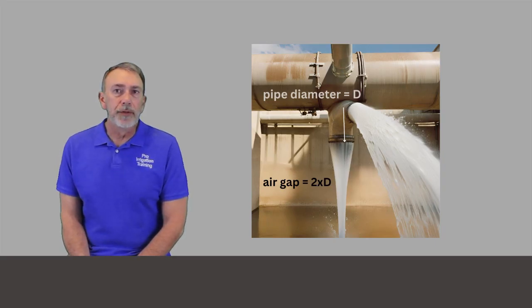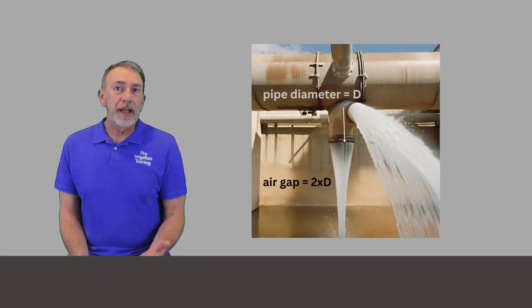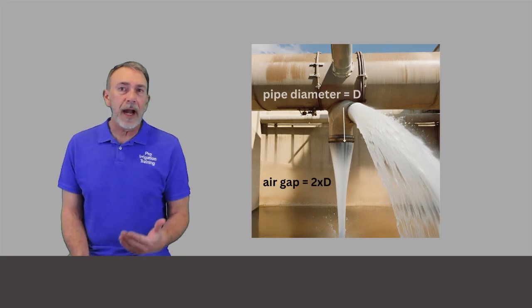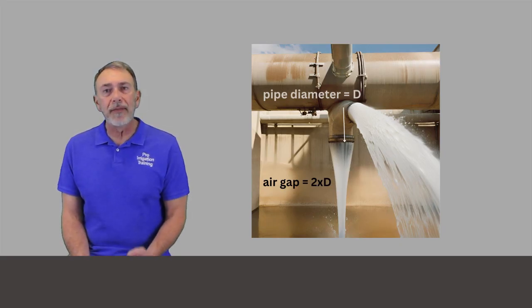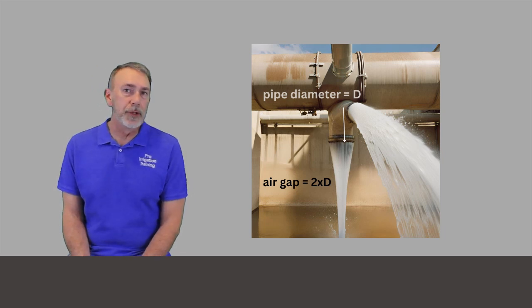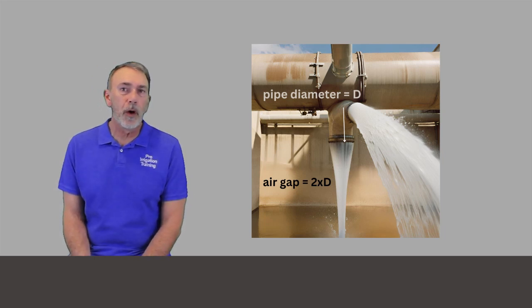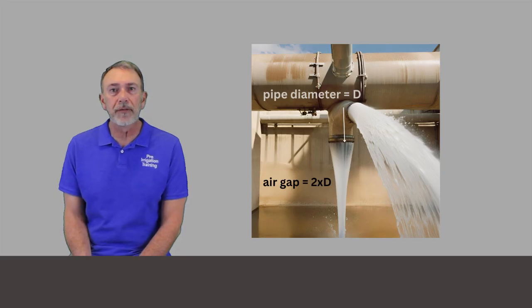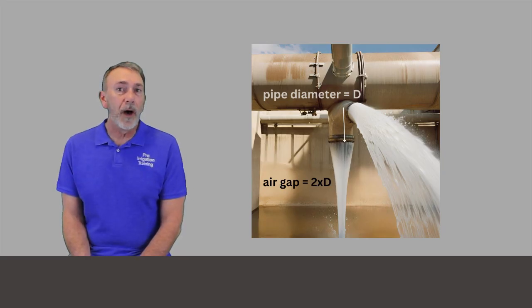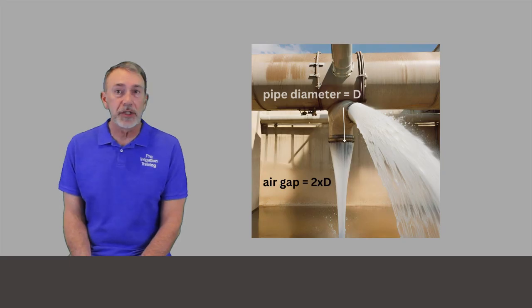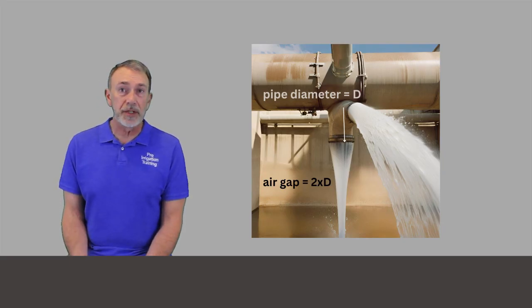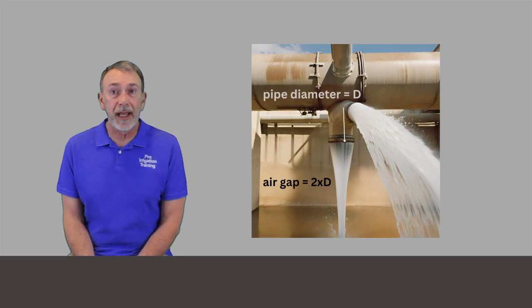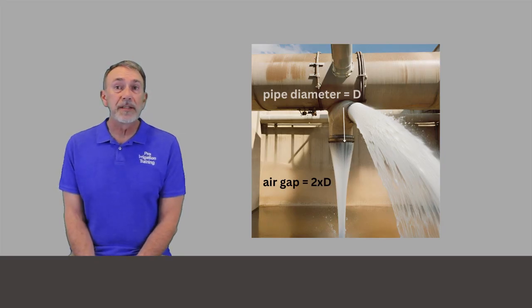So the standard that you have to look at here is the air gap between the end of the pipe and the top of your canister or the level of water or the top of your funnel or whatever it is must be twice the diameter of the pipe. So if you have a two inch pipe here, then your air gap must be four inches. It's two times the diameter of the pipe, no less than one inch.